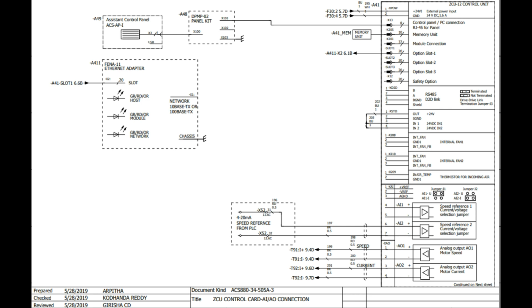Once the drive is running, the PLC must also know at what speed the drive is running and how much current the drive is drawing. For that, we have analog output AO1 for motor speed. This is drive generated. The drive will generate 4 to 20 milliamps, and this signal will go back to the PLC, and similarly how much current it is drawing will show in the PLC. All these settings we do in the drive parameters, so for that you can refer to the different video. We'll come to the next slide.